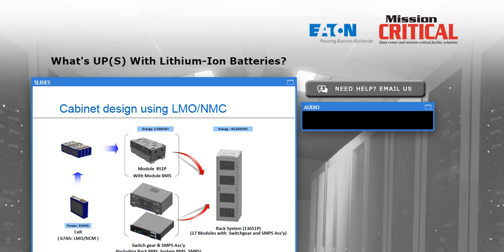What else do you have in the cabinet? You've got a battery disconnect breaker and terminals to land your positive and negative DC signals going to and coming from the UPS. In addition, near the bottom of the slide, there's an SMPS assembly, which is actually the battery management system. It monitors voltages, currents, temperatures, and voltage balance, but it also has the ability to control how the battery operates. And if that battery is not happy, the management system can simply disconnect either that battery or the whole cabinet, automatically and remotely.